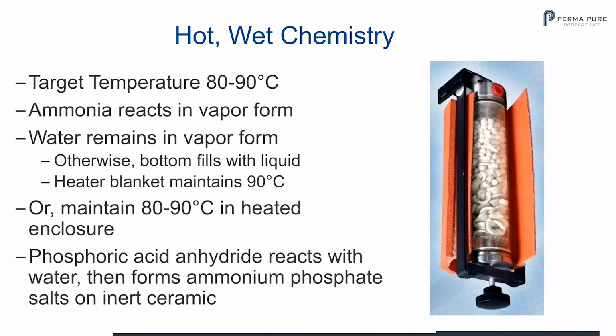So there's hot, wet chemistry inside. The target temperature is 80 to 90 degrees C. Ammonia reacts in the vapor form. The water remains in the vapor form, otherwise it fills up with liquid, so you maintain 80 to 90 degrees C in a heated enclosure. The phosphoric acid anhydride reacts with water, then forms ammonium phosphate salts on the inert ceramic. That's how it removes the ammonia.